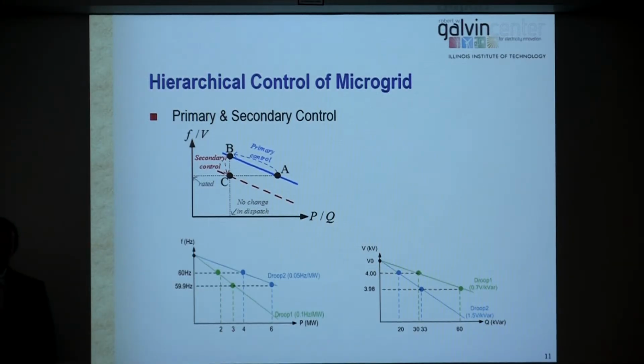The master controller for the campus, we designed it, with all the engineering jargon, scheduling and locational marginal prices, mixed integer programming, and all that went into it. The second level is the building level, with all components within the building connected to that building controller. The third level is device control, lightings in the room and so on.